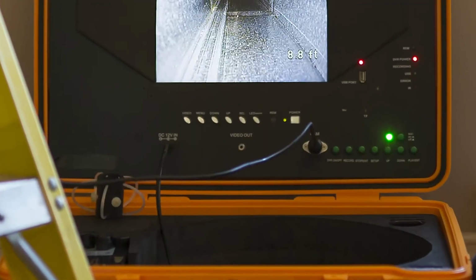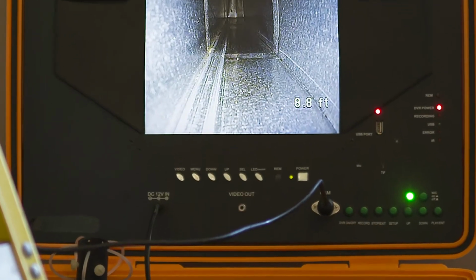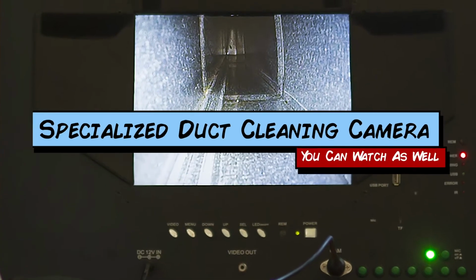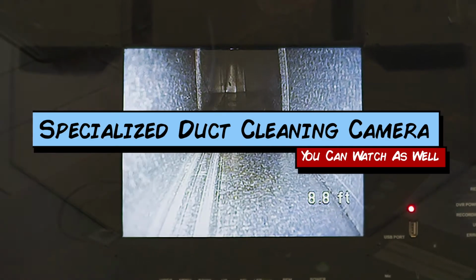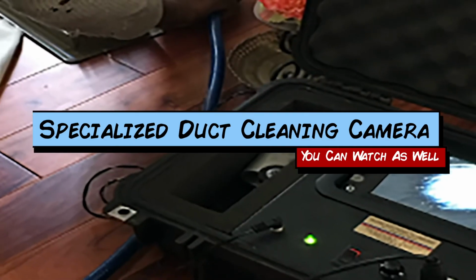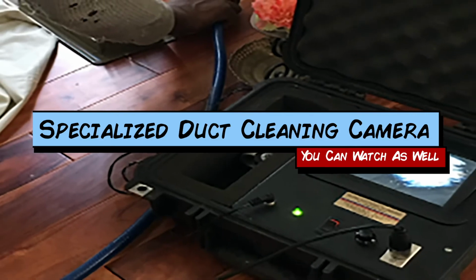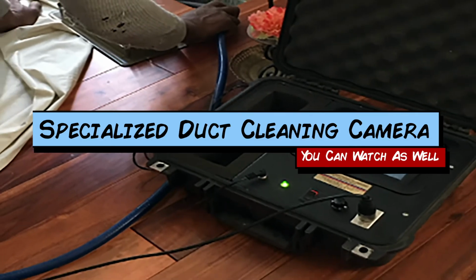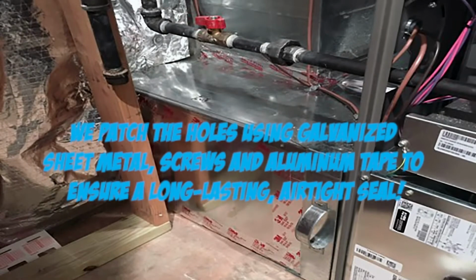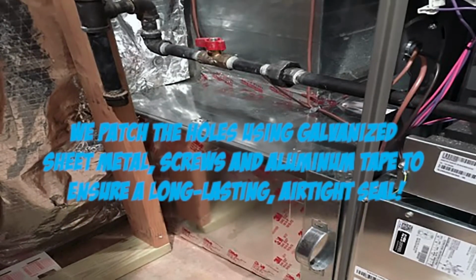Wondering how we can tell what's actually getting removed from the ducts? We've got a camera. Using this live feed device, we're able to check and ensure that everything is being cleared out correctly. We'll even invite you to join the viewing party so you can watch your dirty ducts transform before your eyes. Once the cleaning is complete, we detach the hoses and patch the holes using galvanized sheet metal, screws, and aluminum tape to ensure a long-lasting airtight seal.